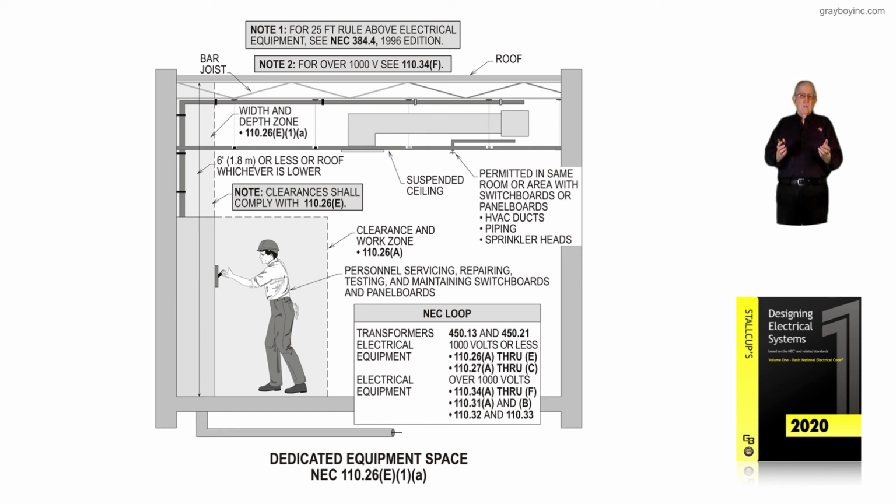And if your job is installing equipment, just look at the voltage. And you'd say, well, it's 277/480. Then in the illustration, the NEC loop, you know where you've got to go and what sections to review. If it's over 1,000 volts, which we deal with a lot of medium voltage, like 4160, 2400, some electricians do today, then you know where to go over 1,000 volts, and there's your sections. So we don't have to know all these sections by heart.